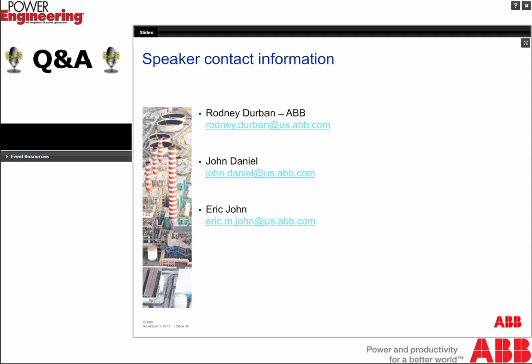I'll move on to question number 35 here. If one of you could take that. Is there a significant loss of inertia when replacing coal with combustion turbines, combined cycles, wind, and solar? John, I'll go ahead and try that one. Obviously, when you retire a plant and the machine changes, you're going to have a change of inertia. If, when you talk about replacing it, you replace it with multiple machines where the total inertia is greater, then it might not be a loss. It may actually be an increase in the inertia that is there. And of course, the performance of the system will change with that.